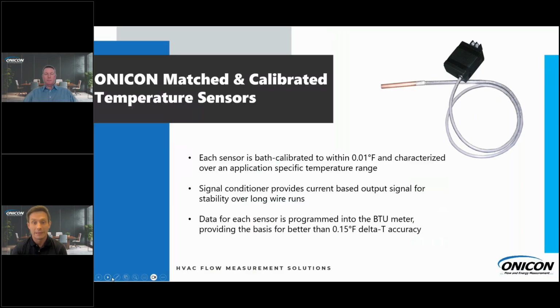How we calibrate this is we calibrate it in a bath specifically for your application. If it's a hot water system, we bath calibrate it in hot water. If it's chilled water, we bath calibrate it in chilled water. These types of sensors offer a very wide range of flexibility in your install runs while maintaining high accuracy. In fact, we found their accuracy is better than 0.15 degrees Fahrenheit across a delta T.